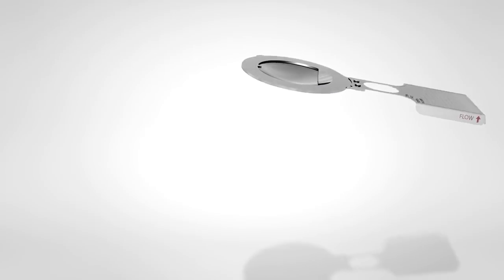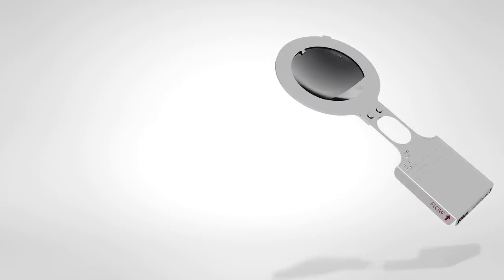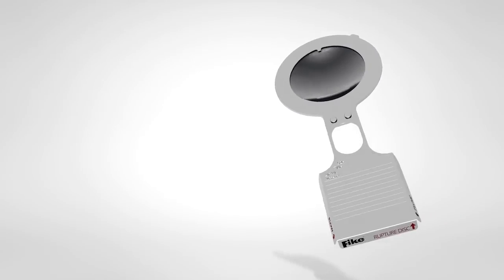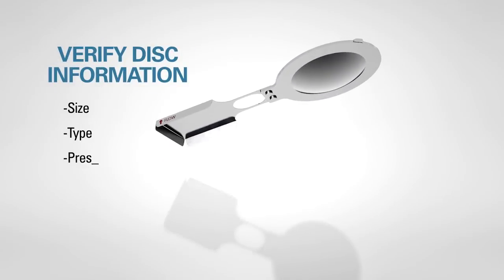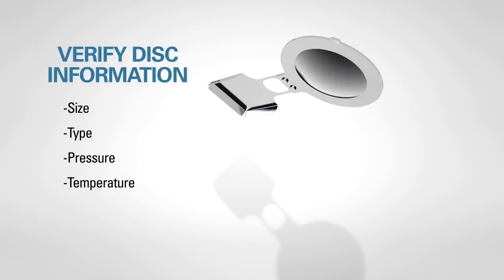Visually inspect the rupture disc for shipping damage. Read the complete information on the rupture disc tag. Verify that the disc size, type, pressure, and temperature are correct for your system.